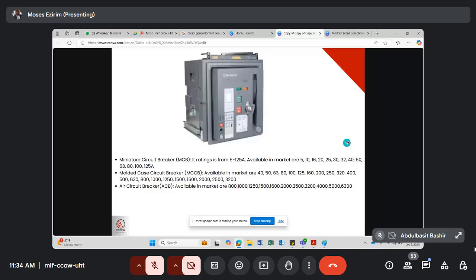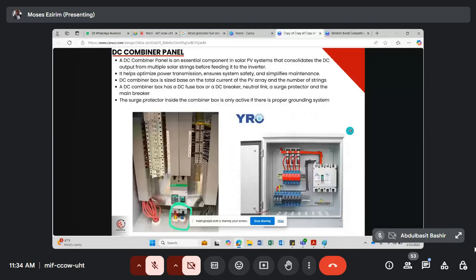So if that is advanced, design this now, I'm going to be using 100 amps. But the 100 amps I'm going to use will be what? MCCB. Because I want everything to, right? Cable as well. So the size of this DC combiner should be what? 100 amps, sizing the inputs breaker based on the main breaker. So at the end of it, you're going to have positive and negative. The positive and the negative will just go straight to your inverter.